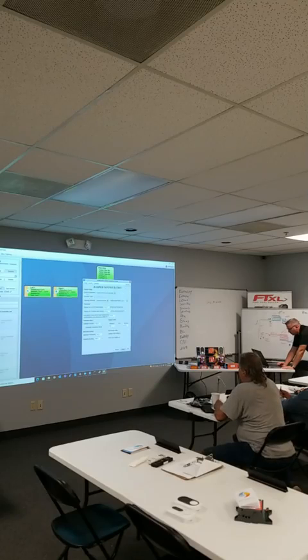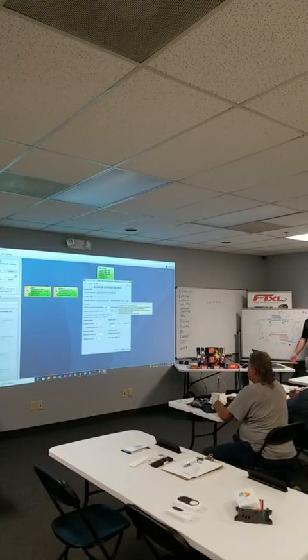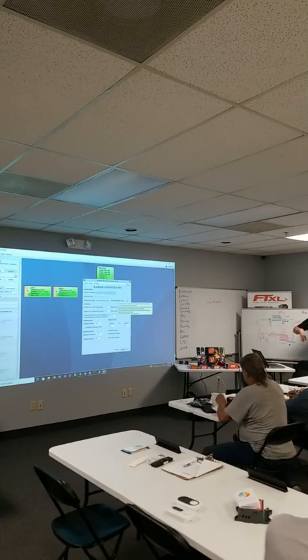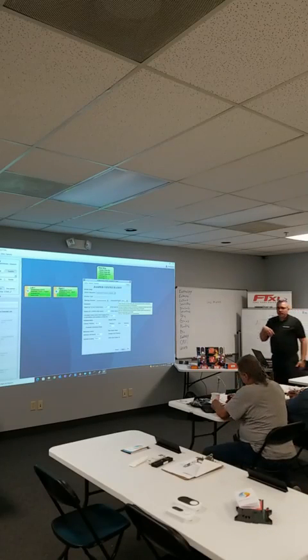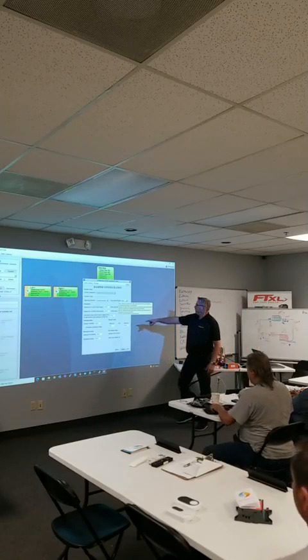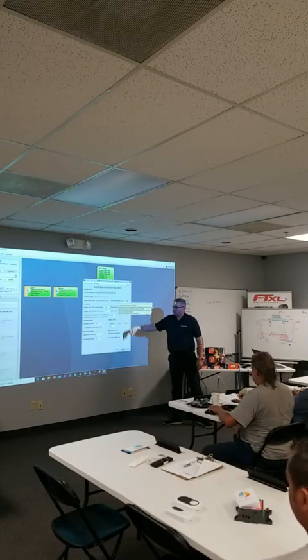When we get into the damper, this controller can also be used for multi-zone, so you just select what it is. You can set clockwise or counterclockwise, and in unoccupied mode you can tell it what you want it to do, whether it opens or closes. Something else the software does is you can hover over it and it'll give you a brief description.